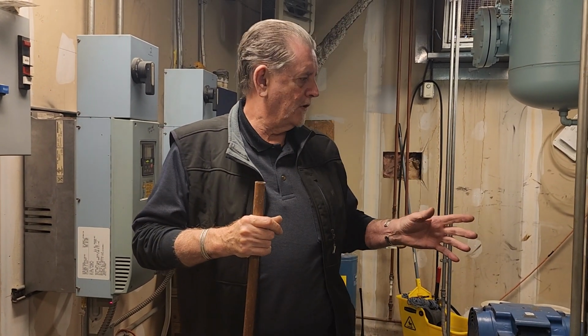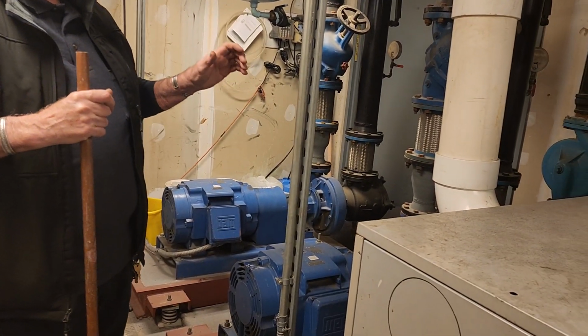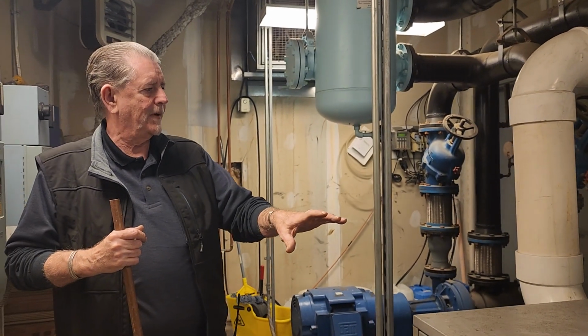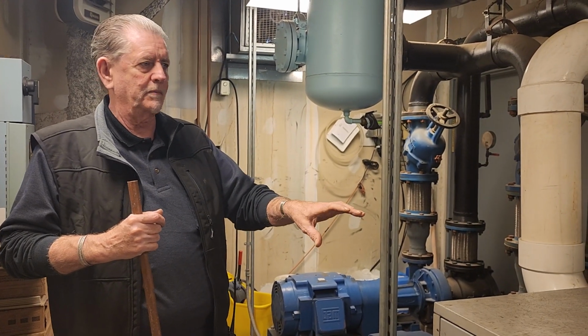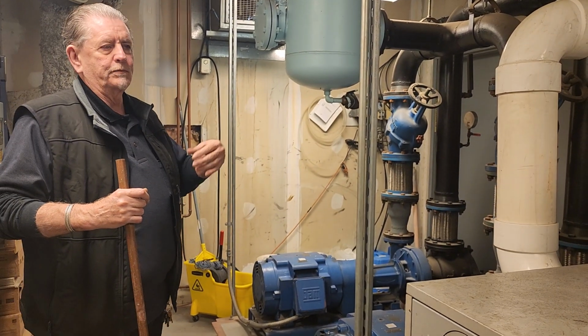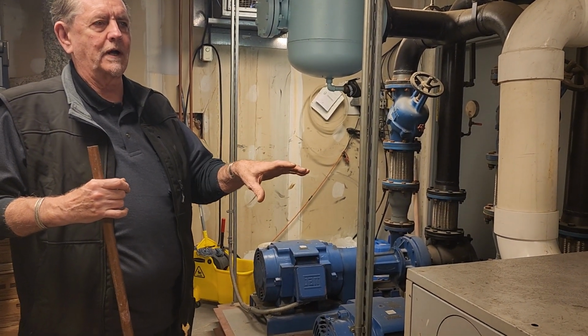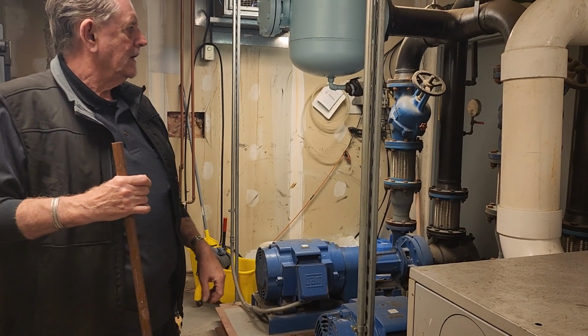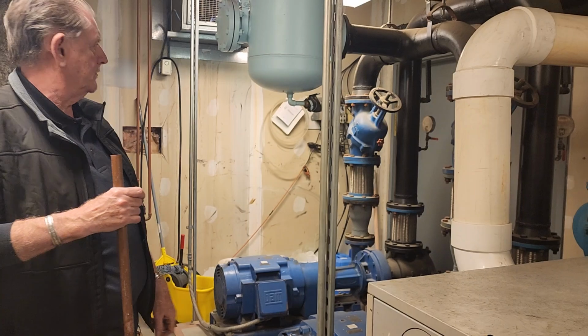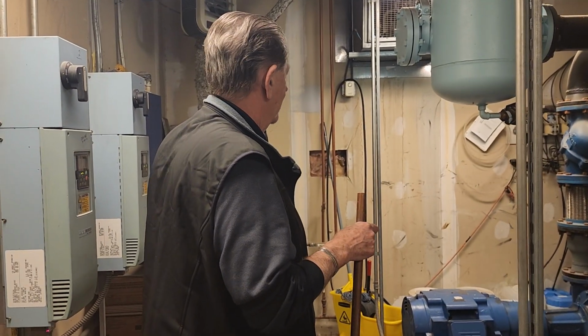You always listen for a noise. These are oilable pumps. Our company comes out and oils these pumps. They basically work on the boilers, service them, change out the igniters yearly. I always believe in preventative maintenance as far as that goes. Whether they need igniters or not, they're getting them. So these pumps circulate the water to these boilers, operated by this system here.